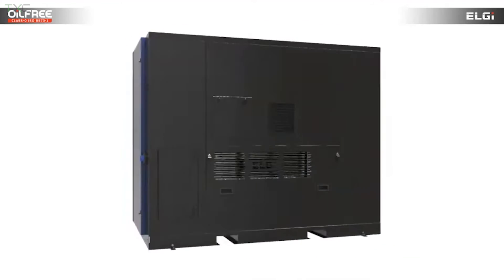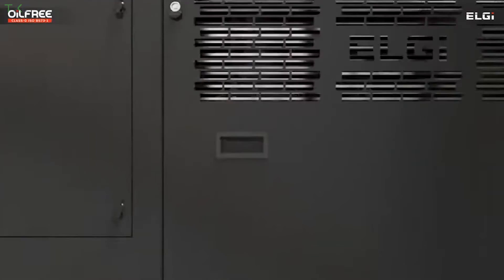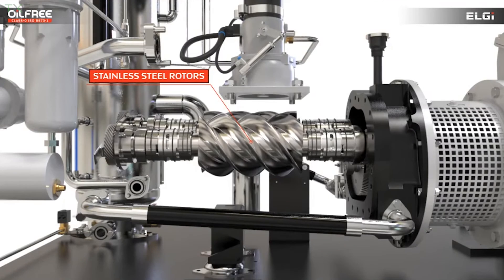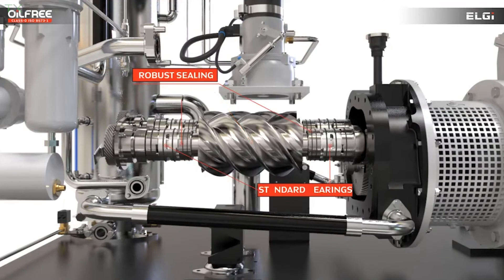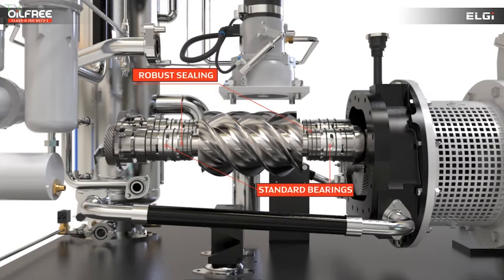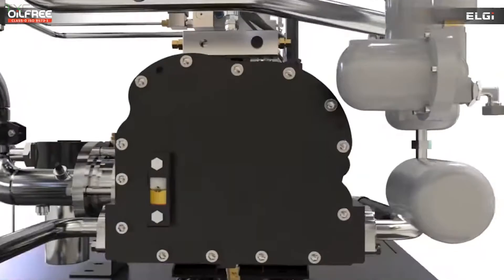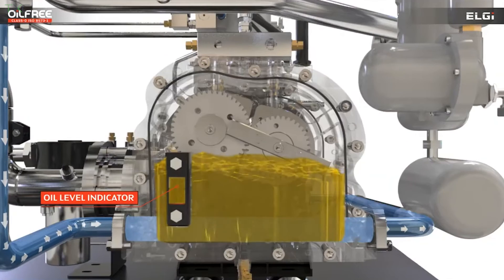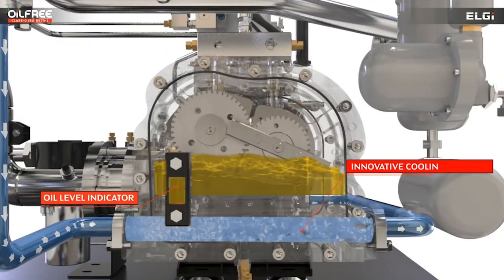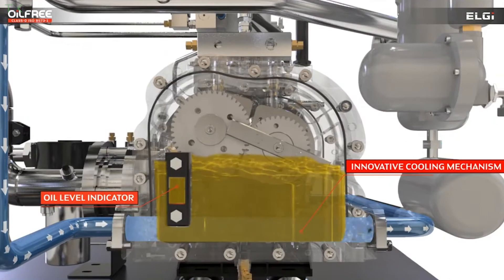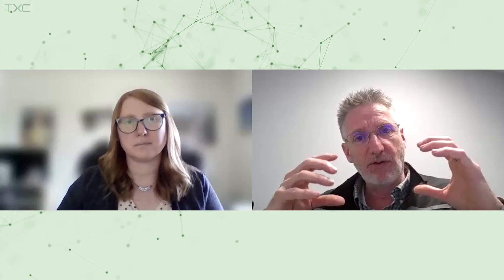So remember, when we started this discussion, when you start looking at the difference between these technologies, the oil-flooded compressor, even though you have all the environmental concerns of oil and the cleanup equipment needed and the maintenance needed to keep those things running smoothly, it's also a lot more efficient. Because you've got that oil closing the distance between the rotor and the housing, it makes the compressor a lot more efficient. You get more airflow out of it.